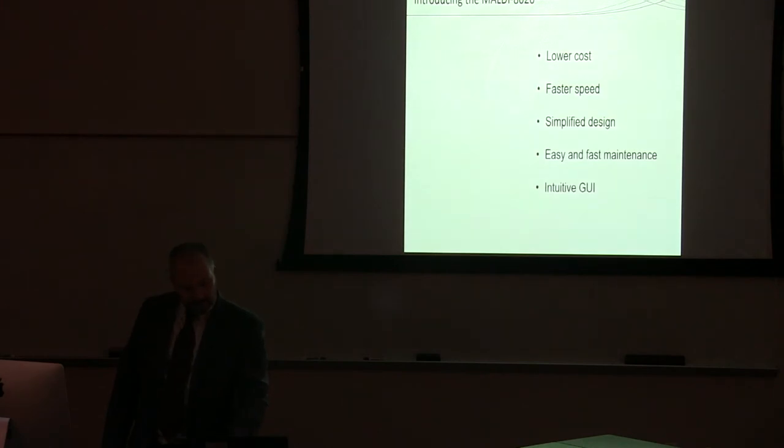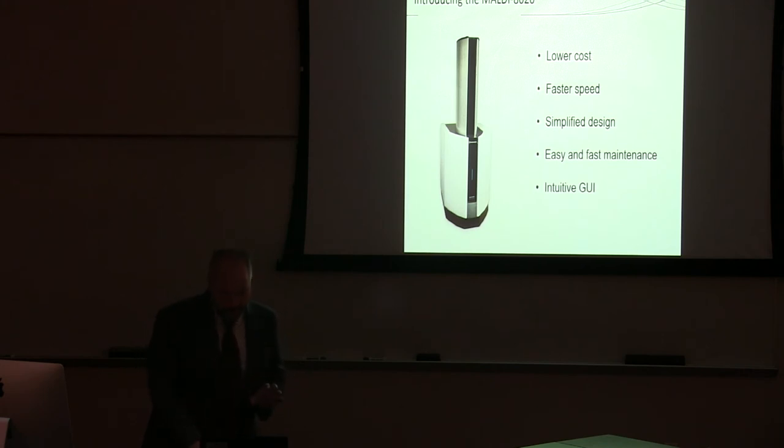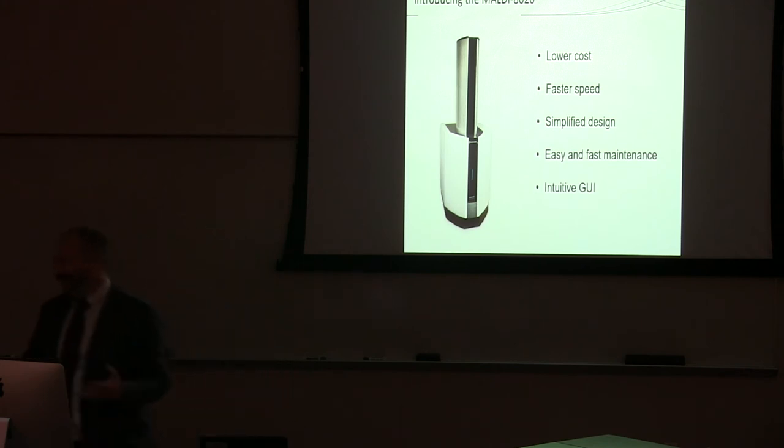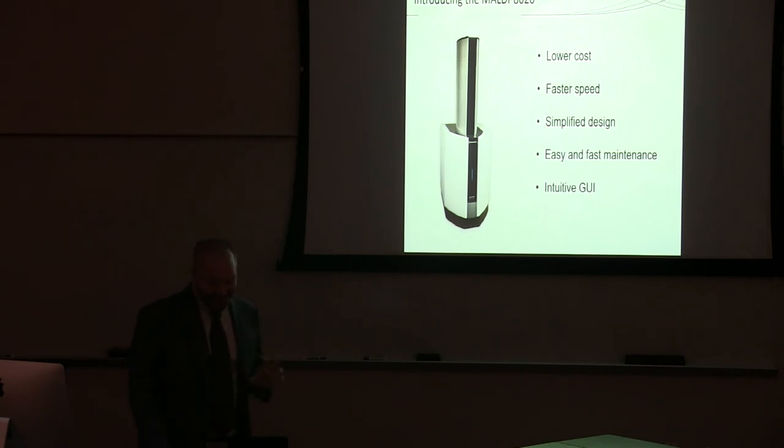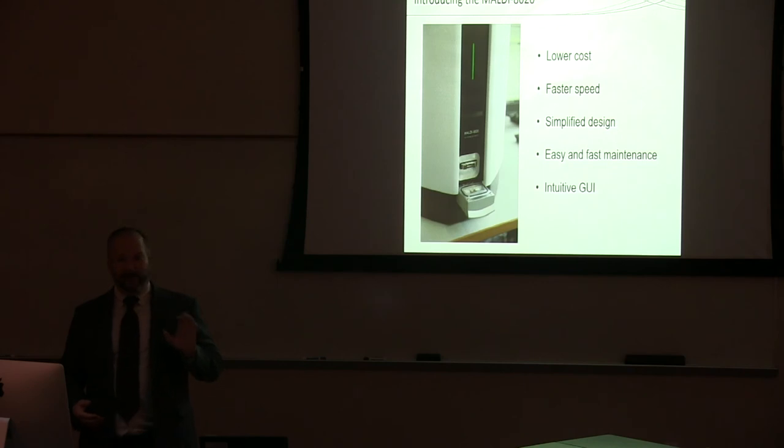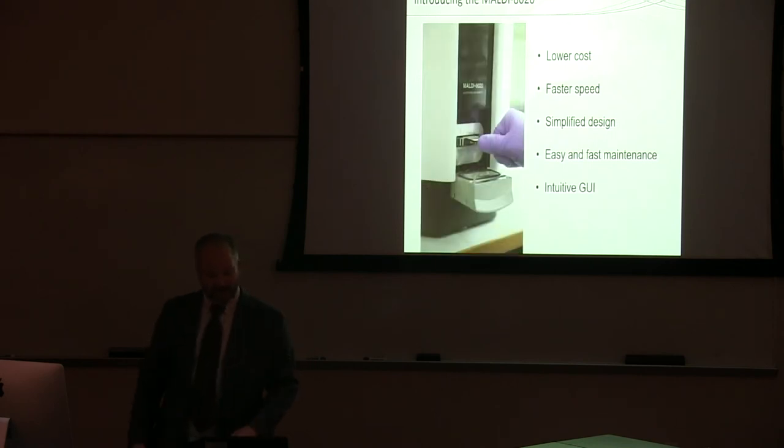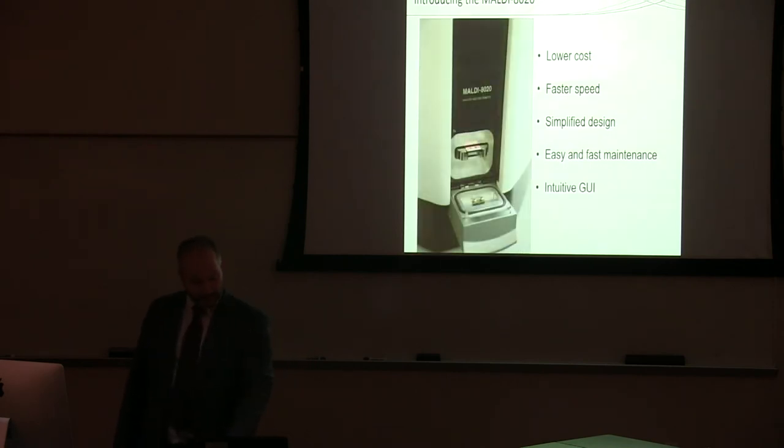And that's going to be kind of based on this whole MALDI-8020 platform, which is the Benchtop MALDI system. I don't know how, we're kind of over time, but we started pretty far into the presentation anyway. But just wanted to kind of showcase some of the nice features of our new instrument. It's pretty inexpensive relative to a lot of the systems out there. Very fast. So this is working with the 200 Hertz laser, and the pump down time is really quick as well. The whole idea of it is to make it a very simple to use instrument.